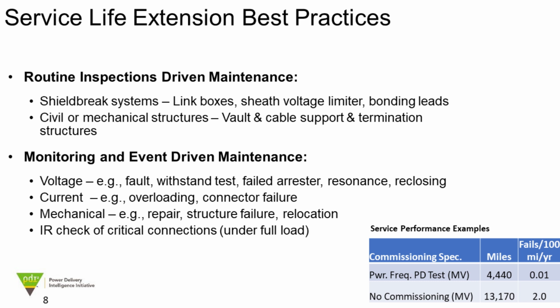There you go. Ben Lance from IMCOR, what do you think about service life extension best practices? Yeah, so really, if we commission the cable properly, we do our training, we do our inspections, we do an effective at or near power frequency partial discharge test in the field, we got a baseline of that asset. Unless there's an extreme event, there's no reason to go back to take a look at that. Reality, if you want to be conservative, we're looking at a decade or two of time frame. The data that's out there now is well over 20 years of experience. The reality is these assets don't move unless they're impacted.